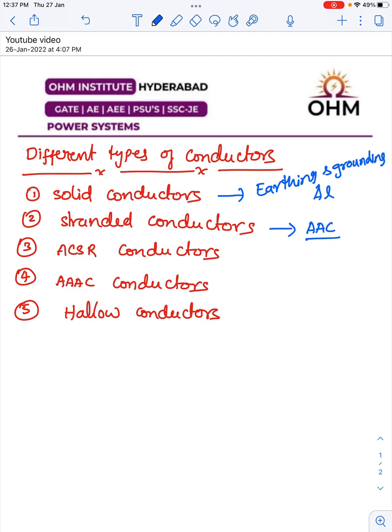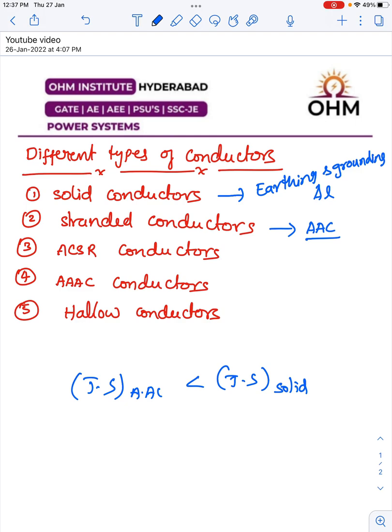However, AAC conductors have reduced tensile strength. The tensile strength of AAC is very much less compared to the equivalent solid conductors for the same current carrying capacity. That is why sag is more, making these conductors not suitable for longer spans — only suitable for shorter spans. So AAC conductors are suitable for the distribution system, not for the transmission system. Double AC means a stranded conductor with all strands made up of aluminum material.